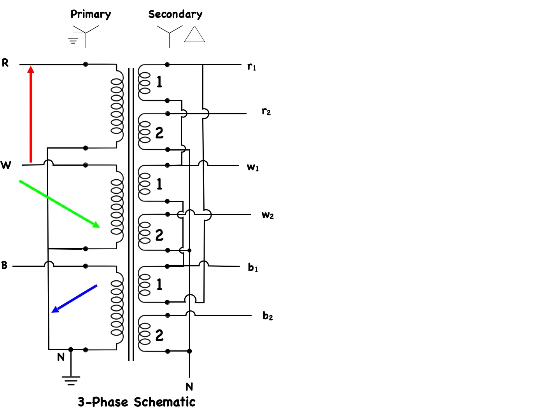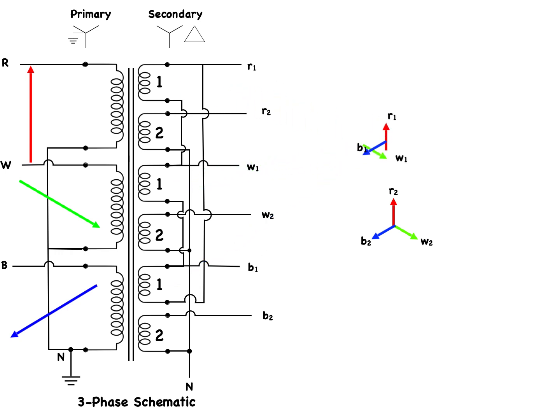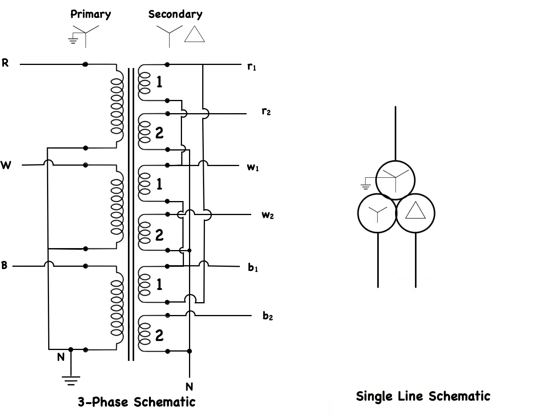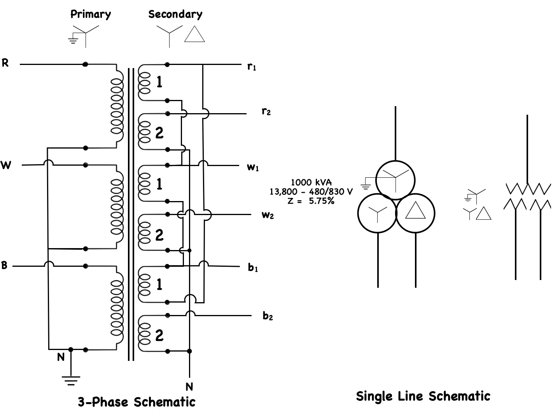Because of the Y connection and the balanced three-phase system, the primary phase-to-neutral voltages will be equal in magnitude but 120 degrees apart. Because the transformer primaries are magnetically linked to each of the two secondaries, the secondary voltages will be in phase with their primary counterparts — for example, the red phase secondaries will look like this. The single-line schematic will look like this, or in alternative forms. The info block shows the KVA reading, line-to-line voltages for both primary and the two secondary voltages, and transformer impedance of 5.75%. This is known as a star-star-delta, or Y-Y-delta, configuration.